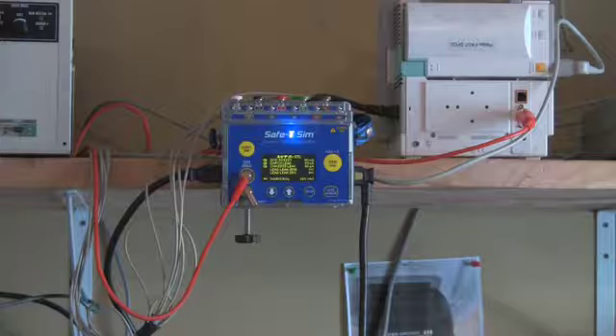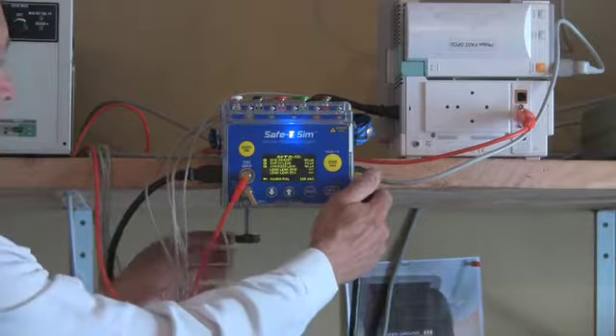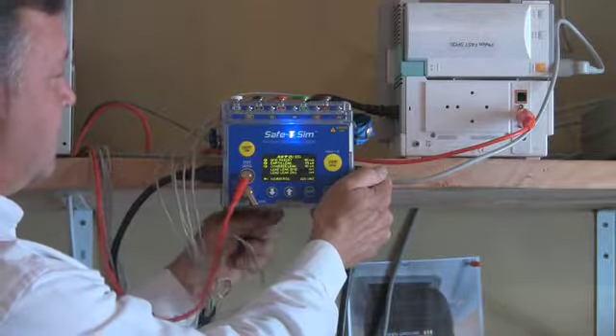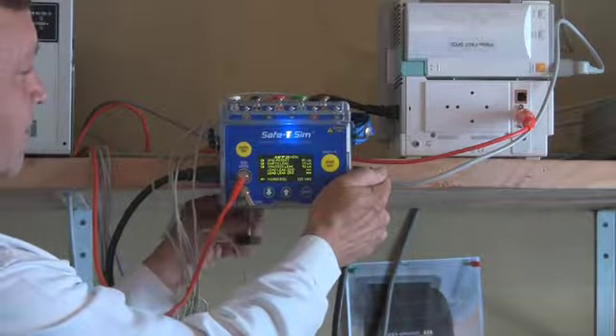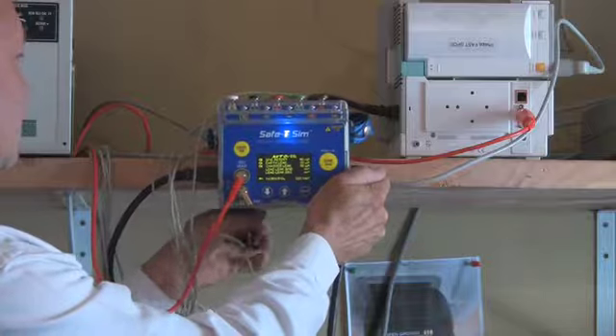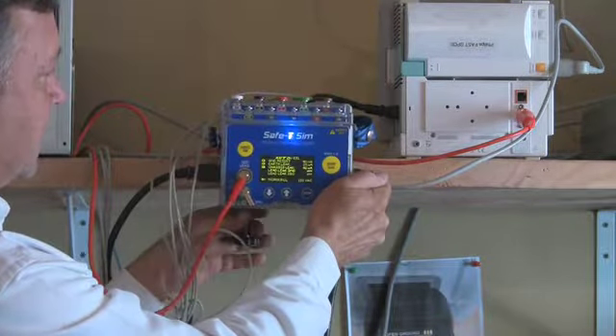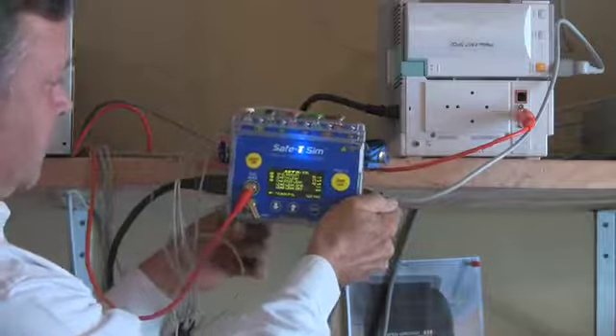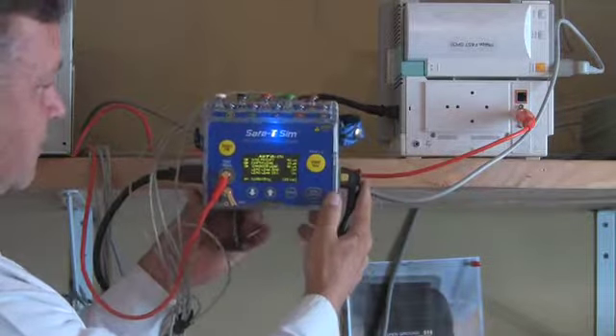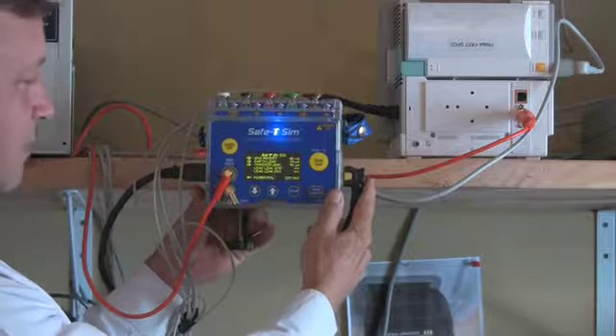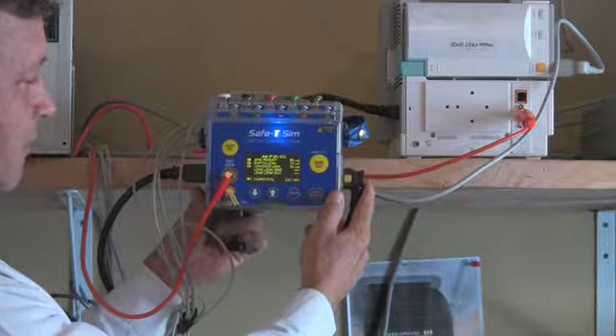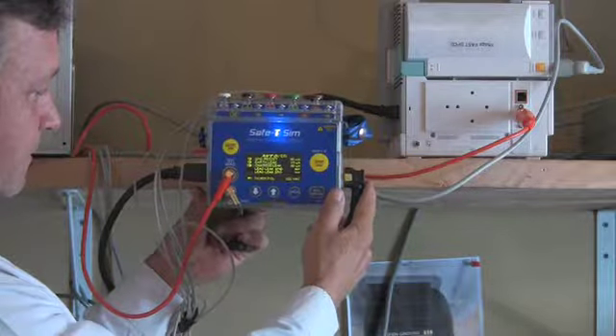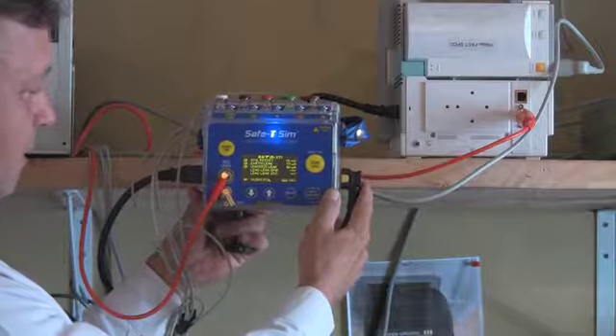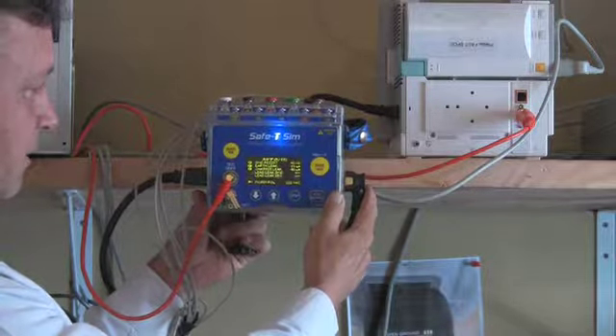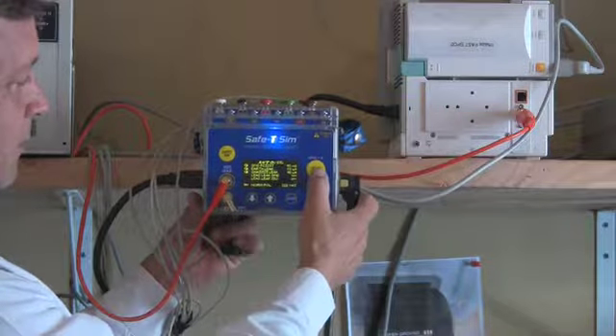One very unique feature that we haven't talked much about on the SafeTSim electrical safety tester is the ability for the safety analyzer to actually detect that it's being dropped. That's important because electrical safety testers have relays in them. If they're dropped and they hit the floor, it can cause a lot of damage to the internal circuitry of the safety analyzer. We put a lot of thought, time, and effort into designing it to be smart enough to sense when a drop was occurring before it hits the floor and actually shut down all the relays inside. That was done with a very accurate accelerometer designed into the circuitry, and a lot of work done on the software side to be able to read that accelerometer and know that the device is actually dropping.